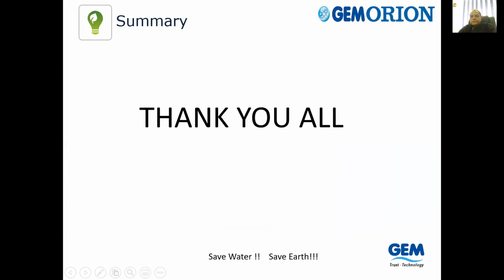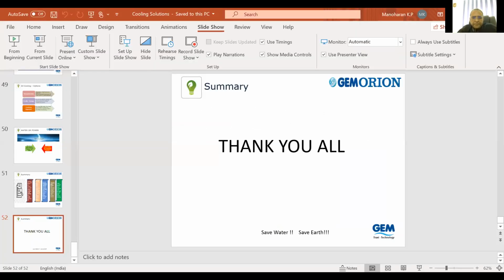Thank you. Thank you, Mr. Manoharan. It was a wonderful technical session on chillers and injection molding especially. As Mr. Manoharan told, the future is going to be dedicated chiller and dedicated machine, because that reduces maintenance issues and also helps water conservation. And especially as India is moving to ICT, information communication technology upgradation in manufacturing, the chillers suggested by GEM Orion have a communication protocol which can use a master chiller and a slave chiller, and all these things are going to happen, whether we like it or not.